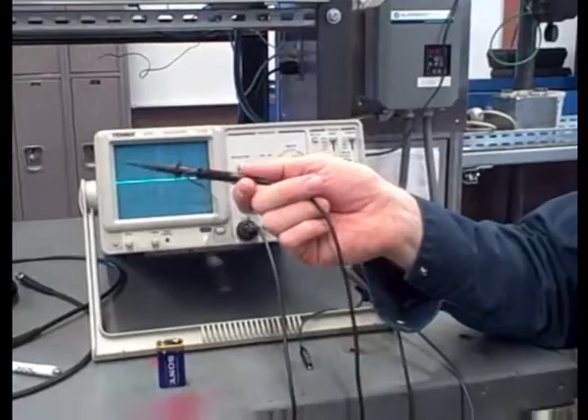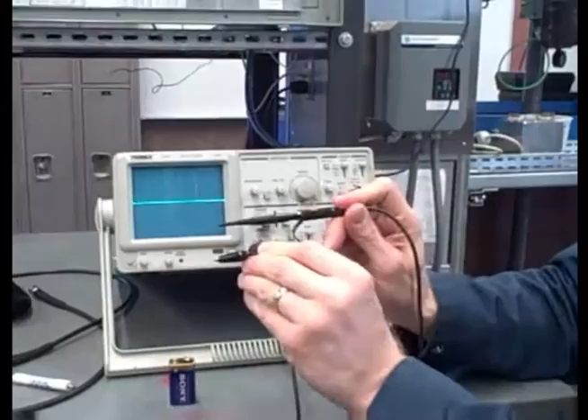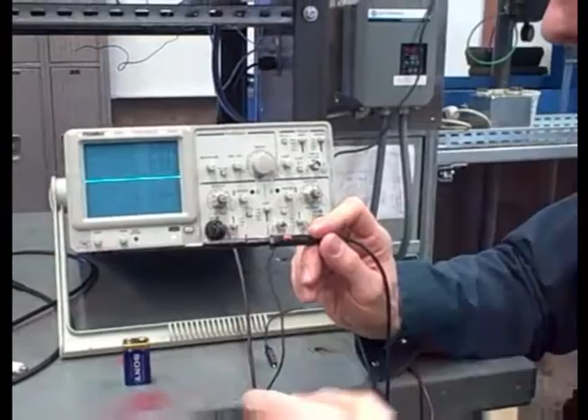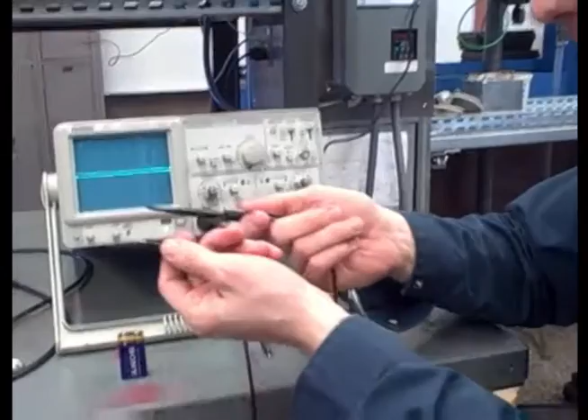Imagine if you were an electrician, you would like to look at the waveform coming out of your variable frequency motor drive that's somewhere around 480 volts phase to phase, and you want to take your oscilloscope and go here to here with it. Well, you're going to have a problem. The most significant problem you're going to have is not the range of your voltage, but rather the fire that you'll be holding as soon as you make the connection between your ground lead and one of those ungrounded phase connections in the motor drive.